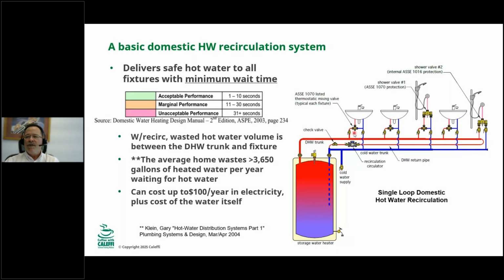If we didn't have a recirc system here, wasted water would be anywhere from the fixture all the way back to the tank. So that can be a lot of water, and you can see this specification here also from Gary Klein, that the average home wastes over 3,600 gallons of heated water per year. And if we were heating from 50 degrees to 120 degrees, and if the cost of that electricity was 15 cents per kilowatt, we'd be spending almost $100 a year in electricity. So that's a significant amount of money. So number 1, the wait time. Number 2, dumping wasted water down the drain. And then number 3, paying for all that. Waste equals money. There we go.